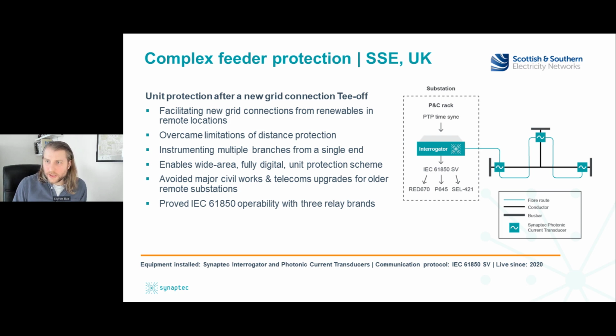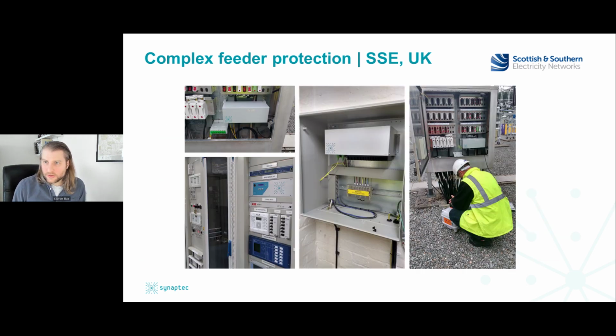Here on the slide, you can see some photos of that installation where we have some sensor units which are installed in kiosks in the substation, and they connect to the secondary of existing CTs. Or as I mentioned earlier, we can connect to brand new CTs if that's needed also. And in this case, the interrogator was providing streaming sample value data to various IEDs in the substation.